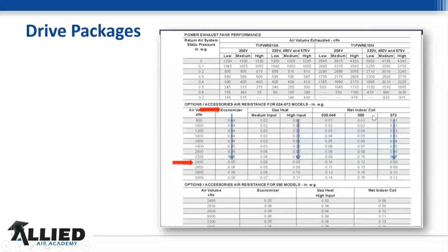So not knowing what an indoor wet coil static pressure is going to be is going to be really important, because you look here from 36 to 48, 60 to a 72. So that's the range we're looking at. And you can see, again, as the air volume goes up, the CFMs go up, so does your static pressure and your static drop. Gas with medium input and high input, it makes a difference. If you look here, you've got 0.5 to 0.8, 0.5 to 0.9. There's a lot of difference in these pressures.